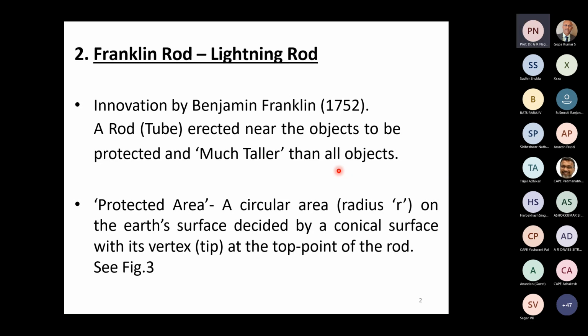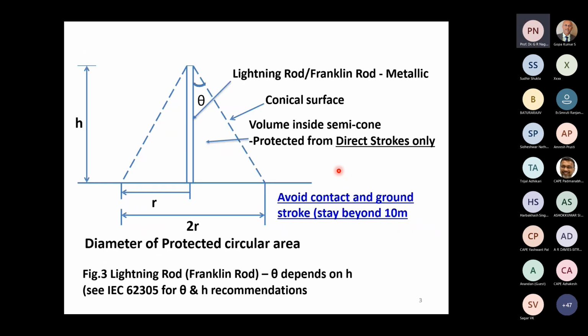For this, we have a principle called the protective angle method for appreciating how this rod works. Now, here in this figure we have a lightning rod or Franklin rod. It's a metallic rod or tube, and then we have a semi-conical volume covered by this cone, which I have shown in dotted lines. The circular area with radius r at the bottom is the area which is protected from direct strokes.